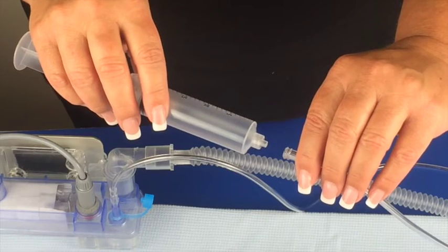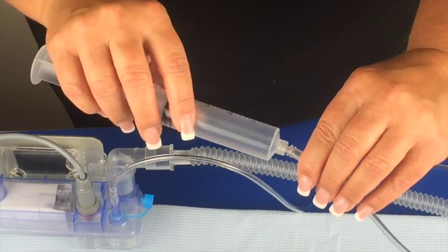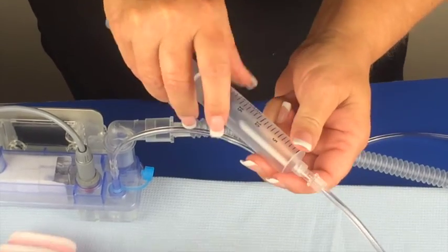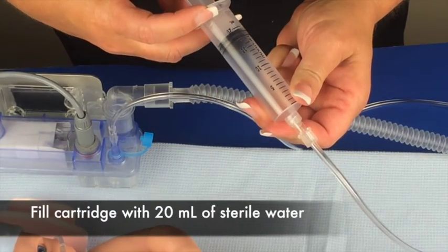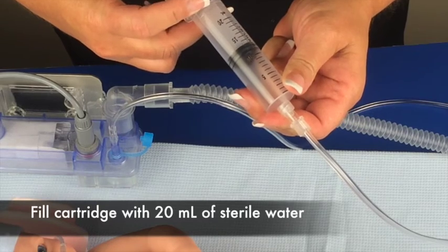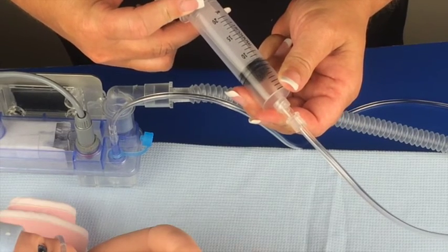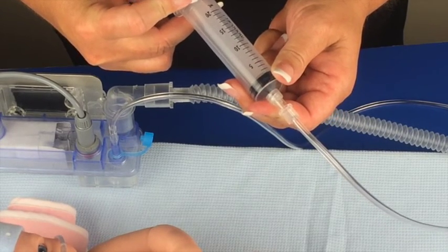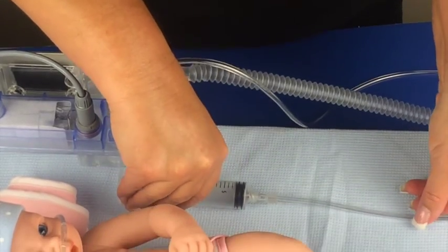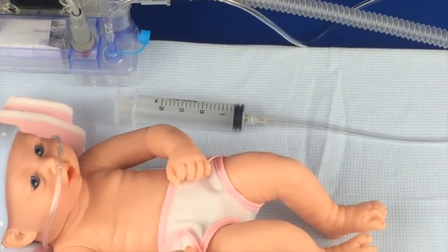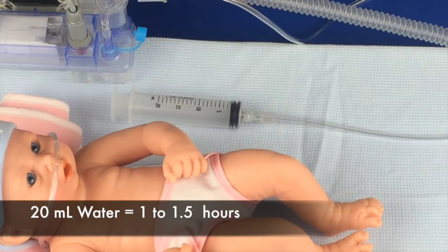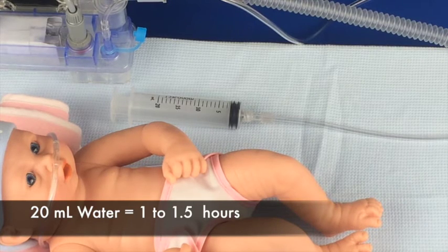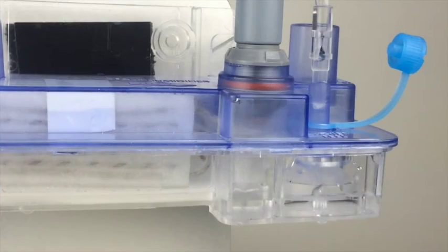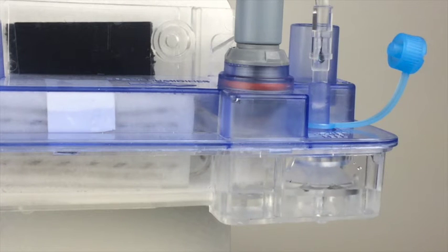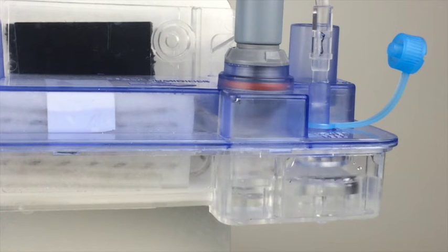Attach the syringe with water to the water feed tubing and infuse 20 milliliters of water into the LavaBed cartridge. Do this slowly. Leave the syringe attached to the tubing for use later if a water refill is needed. This 20 milliliters of water will supply the needs of the LavaBed cartridge for 1 to 1.5 hours. Add more water as needed using the tubing and syringe setup.